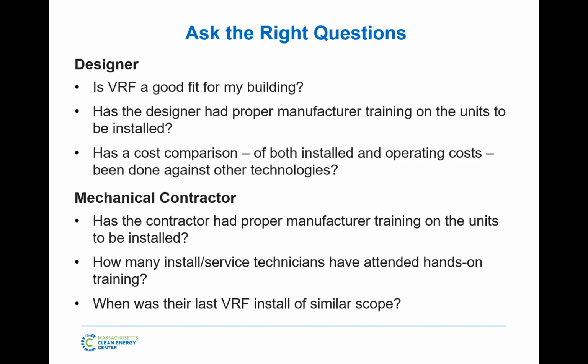The other aspect is, one of the things I answer when somebody asks, what if there's a leak? Well, what doesn't happen is a bunch of water damage. Because if the refrigerant leaks, it leaks as a gas. So that's good because it doesn't damage your building. The bad news is it's harder to find, right? So they're rare because you're using refrigerant copper. The pressure tests are at 550 psi, not 300 like a water source heat pump system. So they're less common than water leaks, but they're a little harder to find. You got to do some testing. Once you find it, you got to fix it, take your system down, and all that stuff. I'll let you address it.